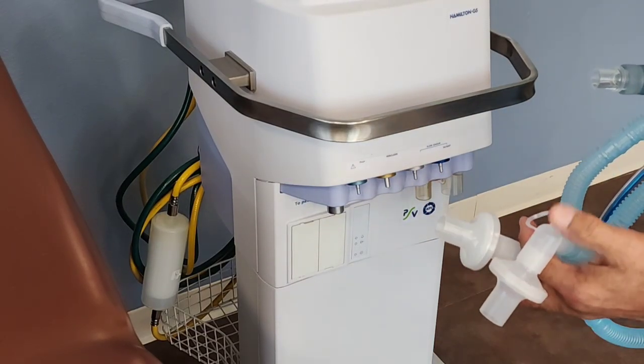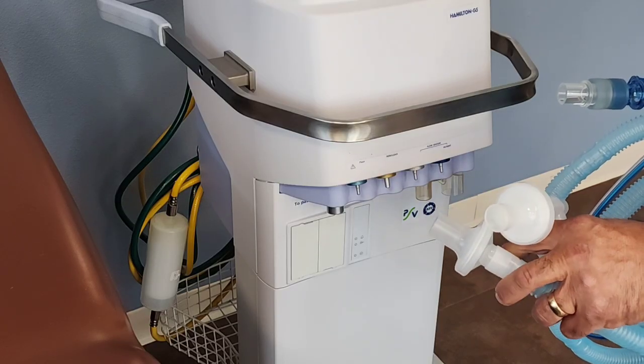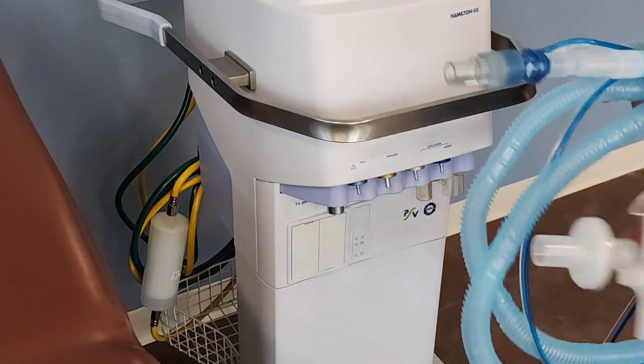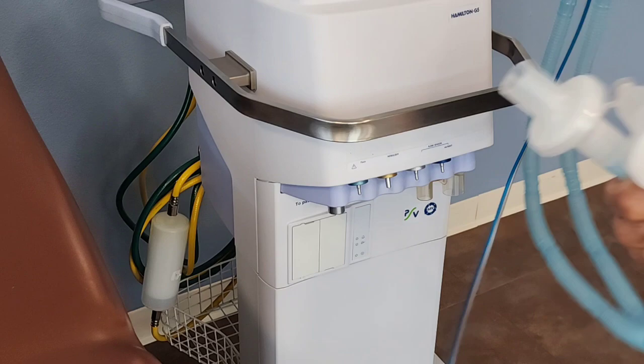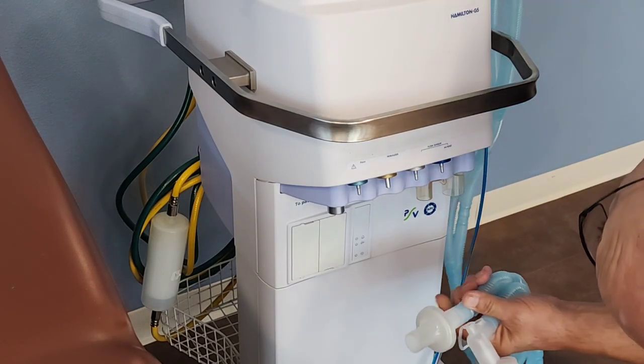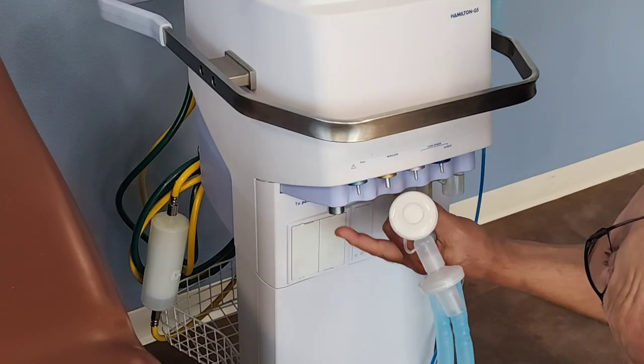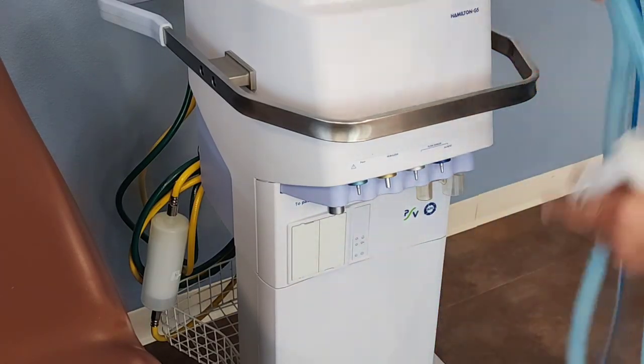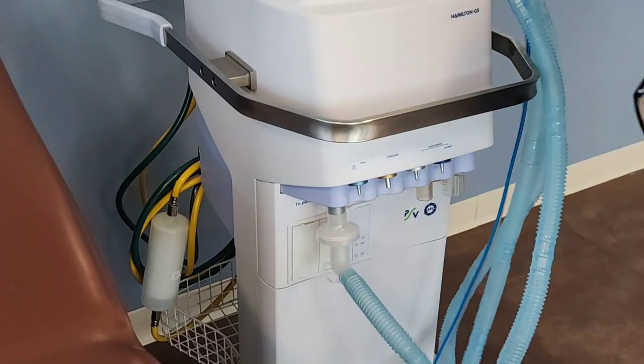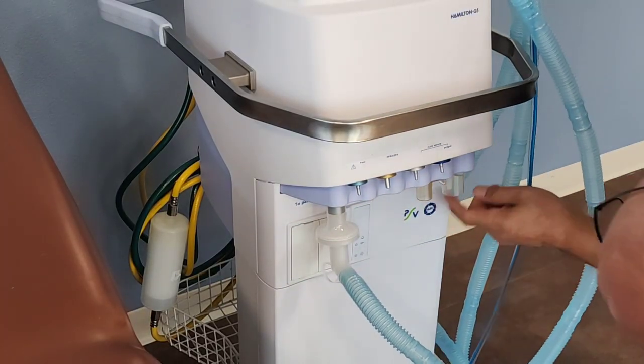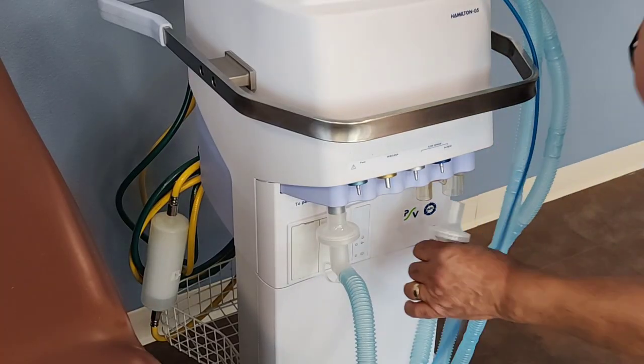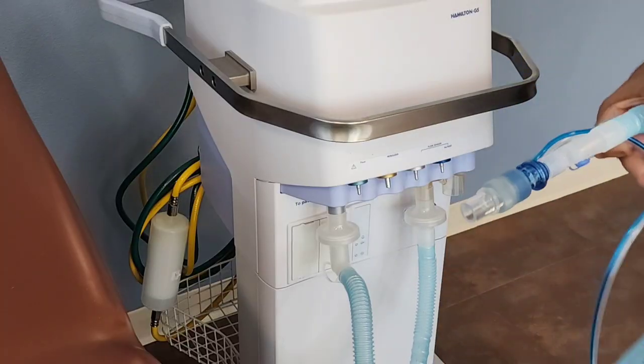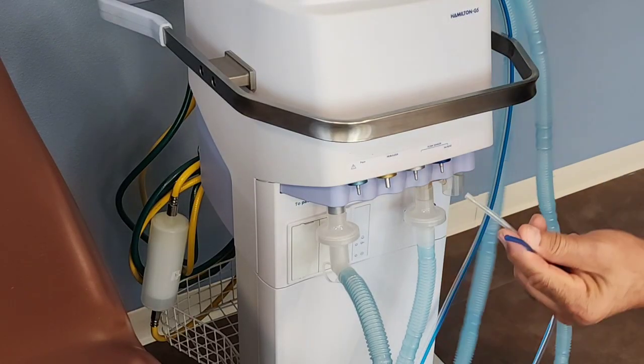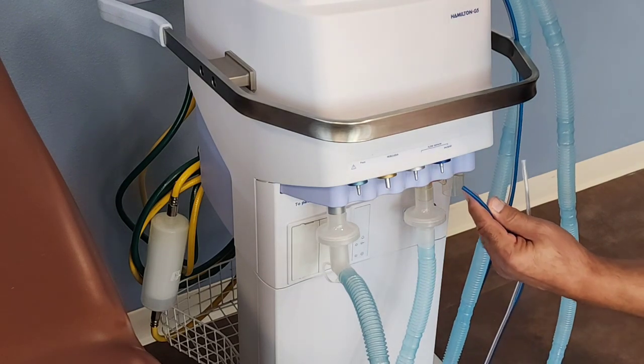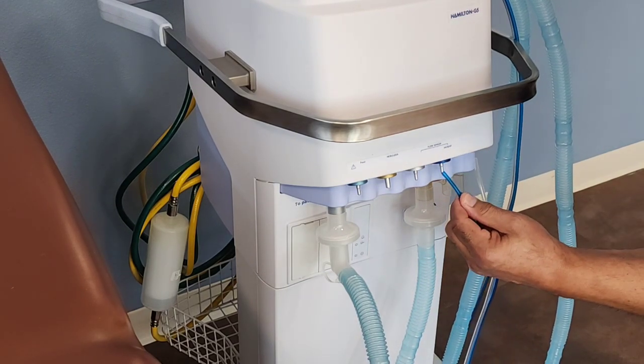You can see again, this is the inspiratory going to the patient. Okay, so let me connect these here. I might be touching the ground on these because this one does not have an arm to hold anything. So under here, right down here, it says to the patient. So I'm going to connect this one here to the patient. And then this one here says from the patient, so I'm going to connect that right here. Then you have the flow sensor tubing, and they're color coded, one blue and one clear. And the blue goes to the patient, it says here. Connect that.